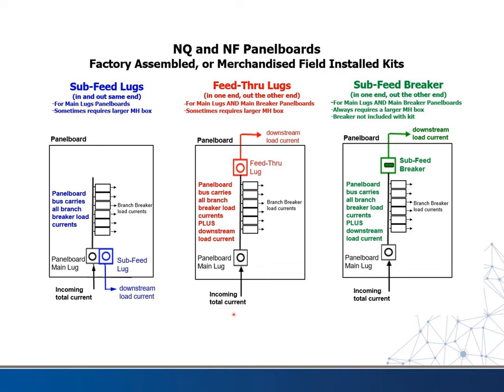Now we can have feed-through lugs, where in this case, we still have our incoming feeder coming into this lug. It goes through this bus, which feeds these breakers, but then we put lugs at the end and connect and go downstream. So this is sub-fed lugs, this is feed-through lugs.